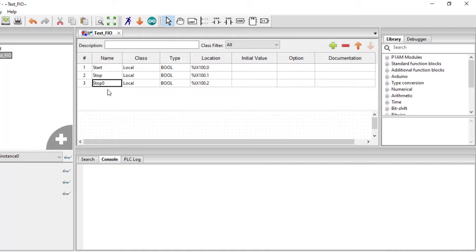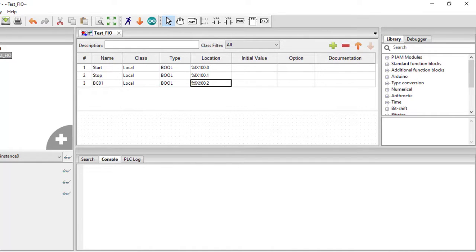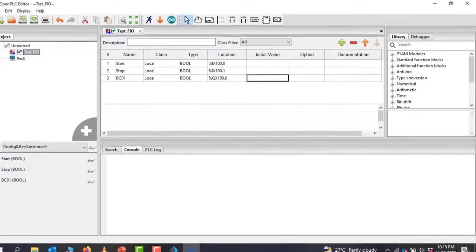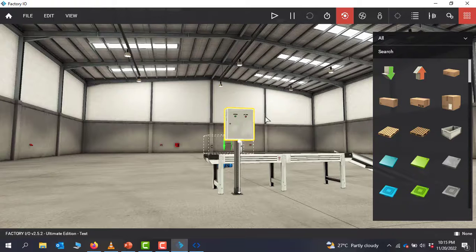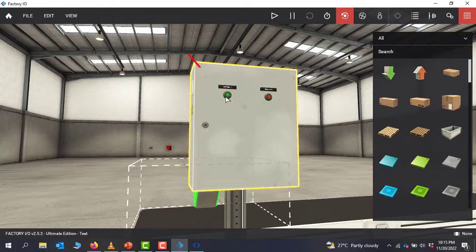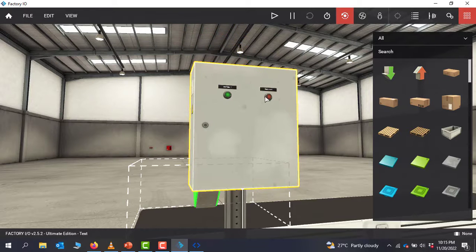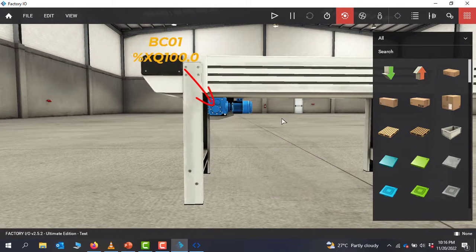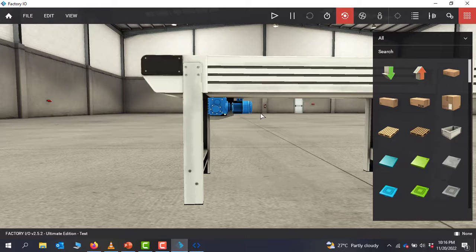We then add our last variable which is going to be our conveyor — we'll call it BC01. It's going to be an output, so we need to change the address to QX, and it's going to be our first output: %QX100.0. Looking at Factory IO, this is going to be our Start button, we've named our Stop, and the motor which drives the conveyor will use a contactor energized using the output QX100.0 that we've already defined.